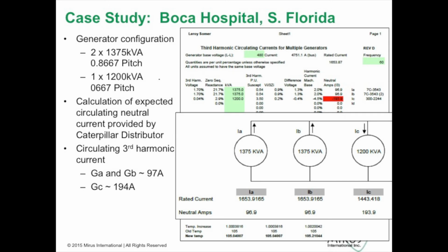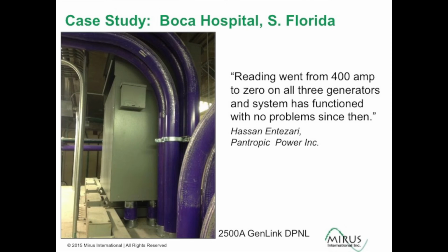So you can see here in the spreadsheet from the generator manufacturer, they're expecting just under 100 amps of current in the neutral on each of the existing generators, and all of that returning to the new parallel generator, of just under 200 amps. When we totaled up the total kVA capacity of the two generators, it came to a 2500 amp DPNL, and that was installed in the system. We didn't get a chance to go back. You can see the installation here of the unit.